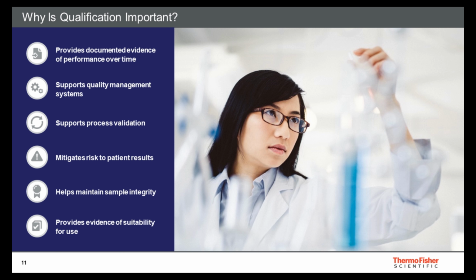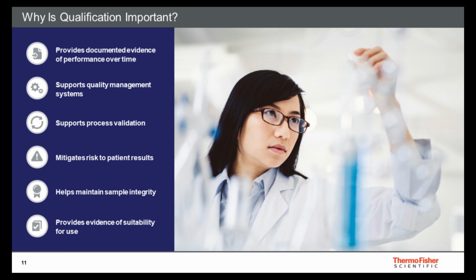I was assigned the investigation of a for-cause action of a medical device manufacturer based on an MDR, or medical device reportable event. The MDR reported was on a clinical lab who supplied results to a hospital where a patient was injured through a prescription of an incorrect therapeutic. Because the clinical lab maintained excellent device history records with qualifications, sample processing, and operator use, the investigation was quickly able to narrow down the potential impact. Between the medical device manufacturer and the clinical lab, we established what instrument, what operator, and what sample was in question.